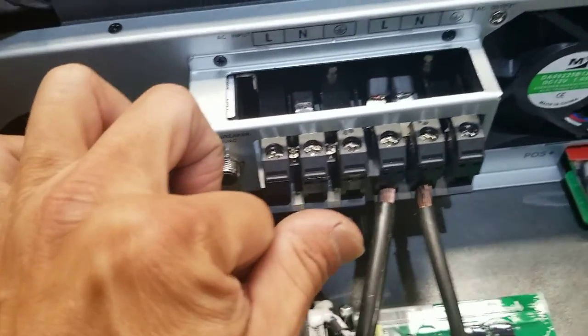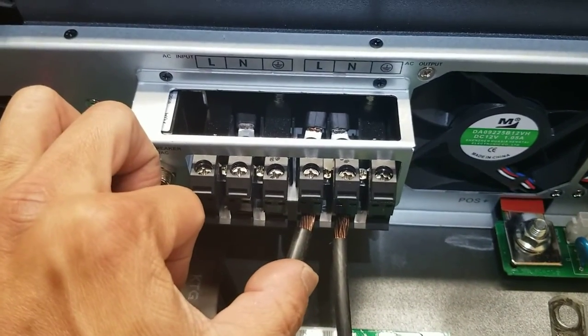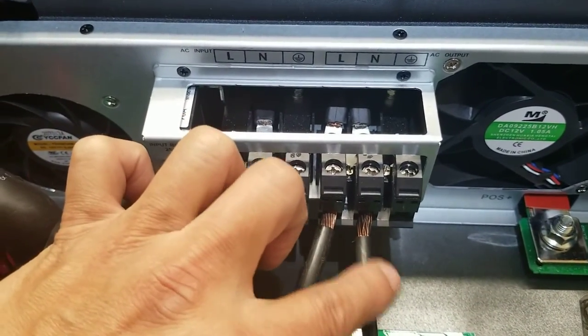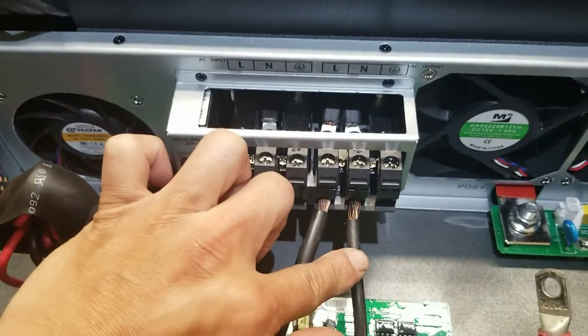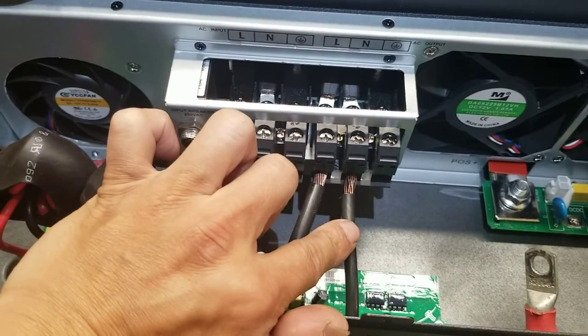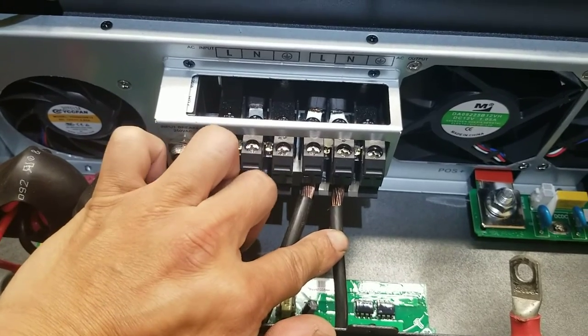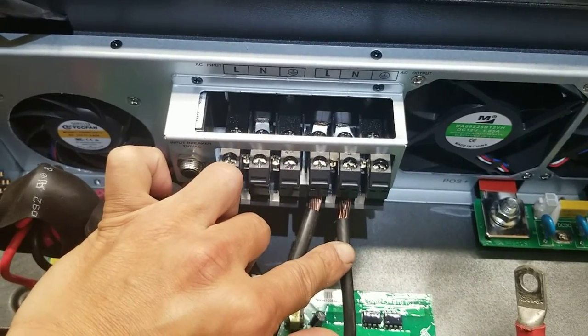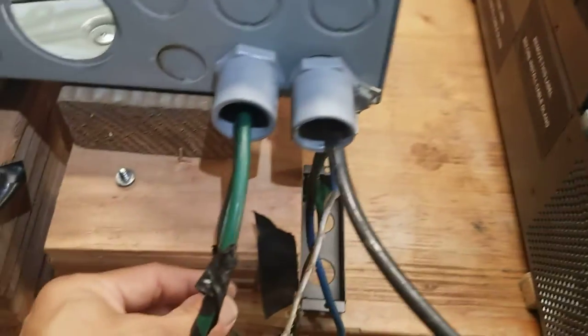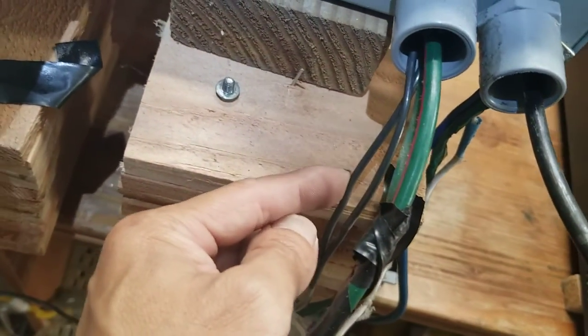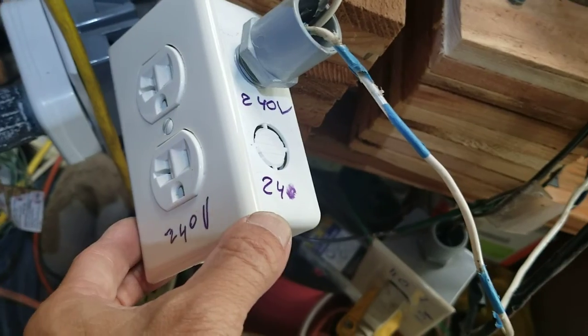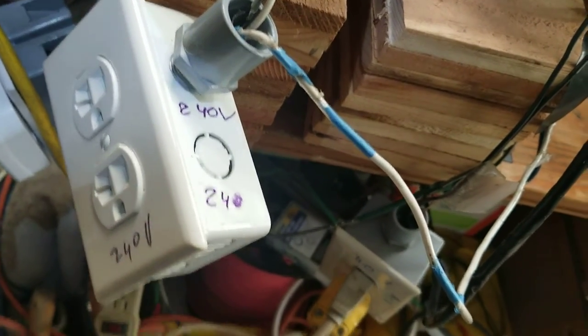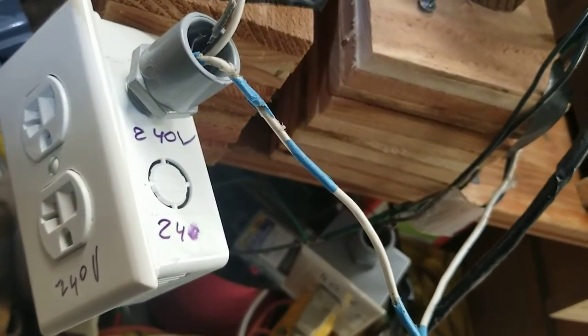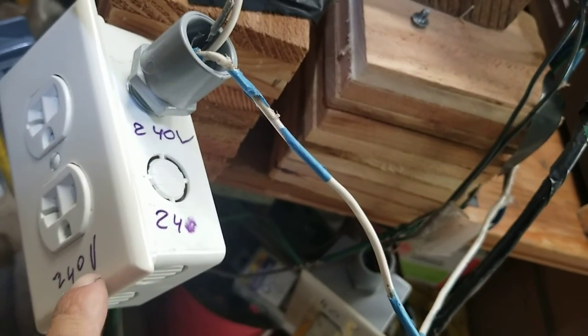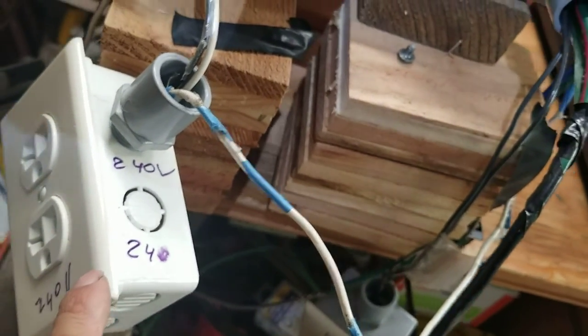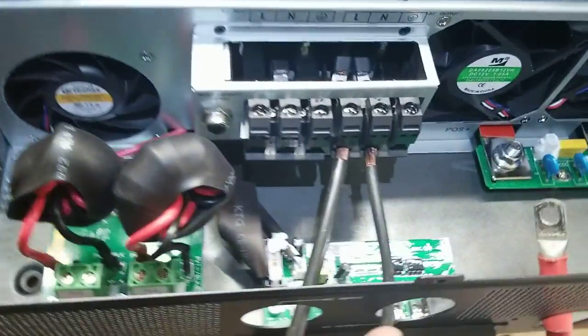The rule of thumb is 80% — you can only use 80% of the conductor's rated capacity. So for a 20 amp wire for your outlet, you only use 80% of that. 80% of 20 is 16 amps.